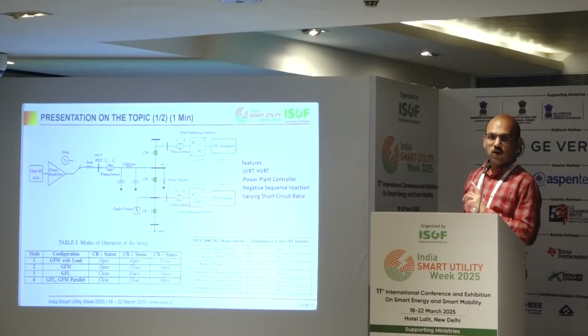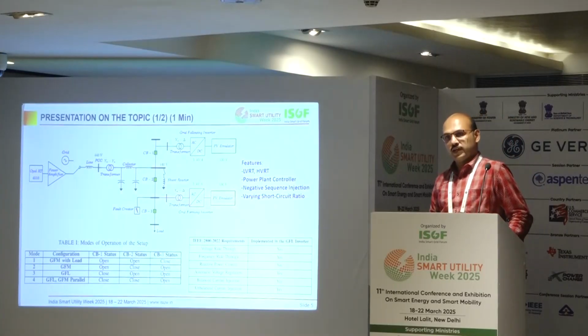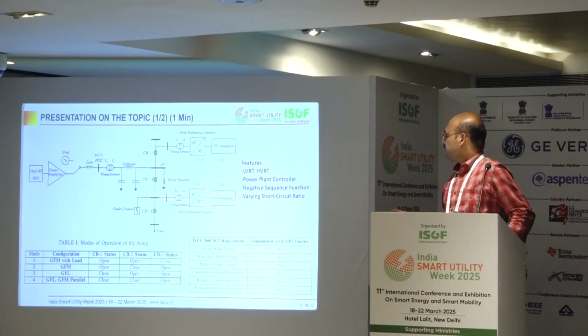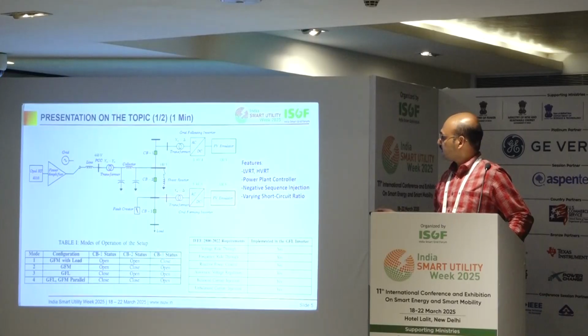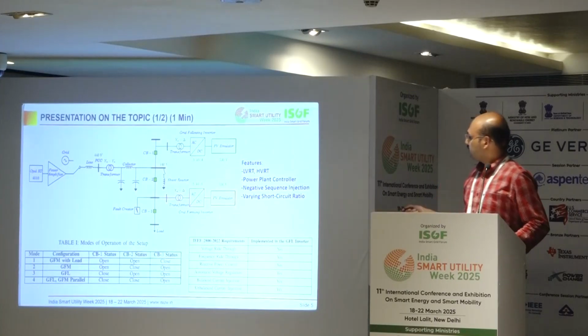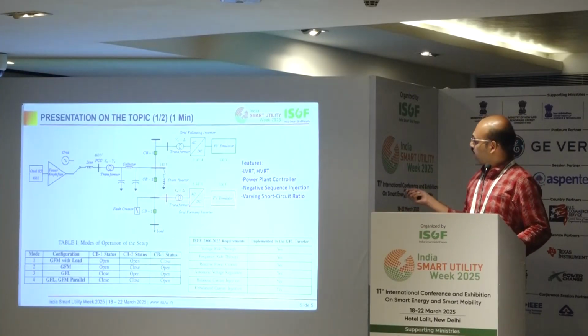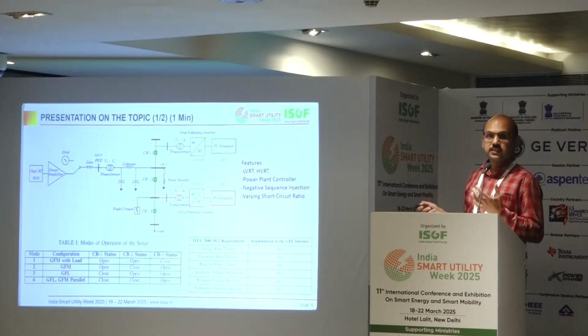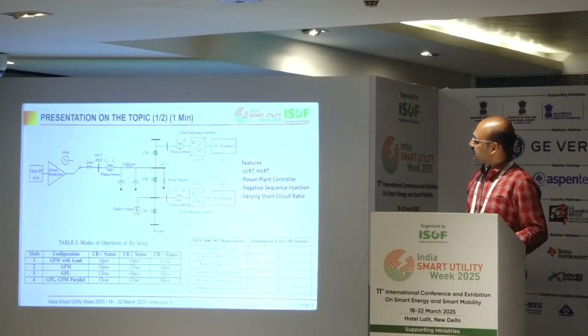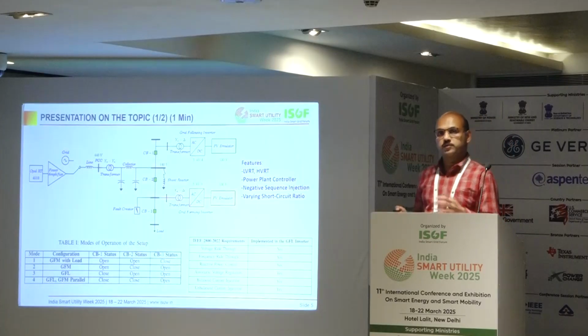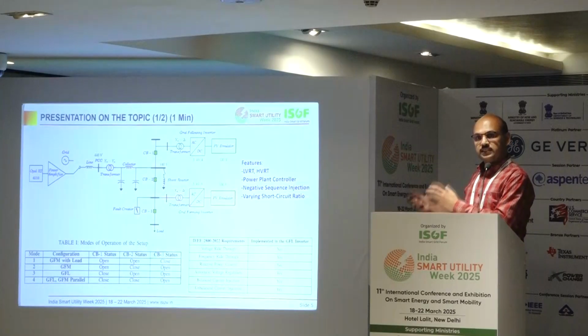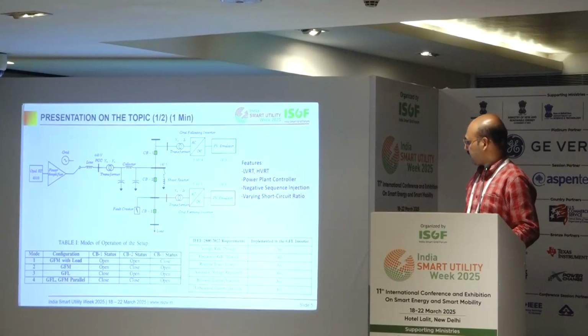As for the features, all these are IEEE 2800 compliant, especially the grid following inverter. LVRT, HVRT is there. We also have a power plant controller at this point. That controller is giving set points to the grid following inverter. Then you have negative sequence injection from both grid following and grid forming. Then you can study, especially the weak grid scenario, by changing this line impedance. You can create various short circuit ratios, and you can see the behavior of this PV plant.